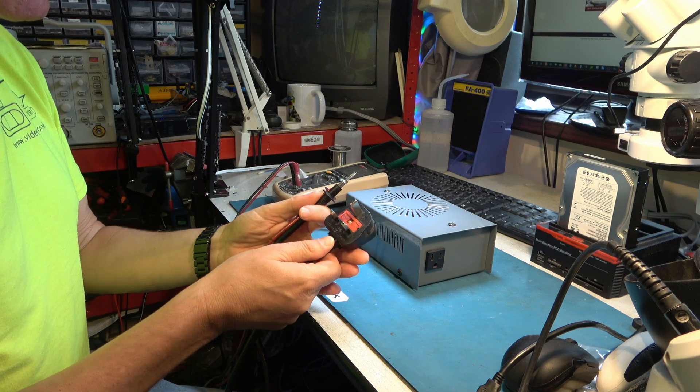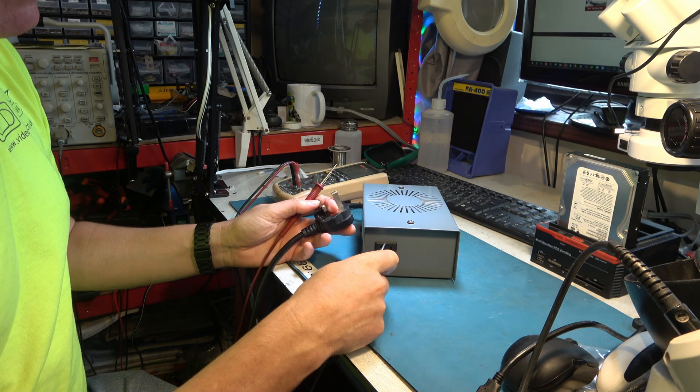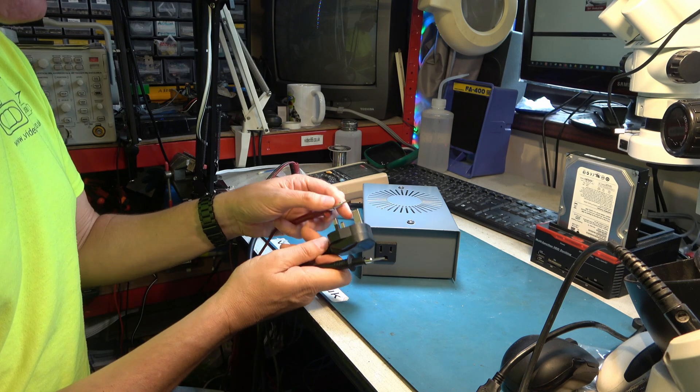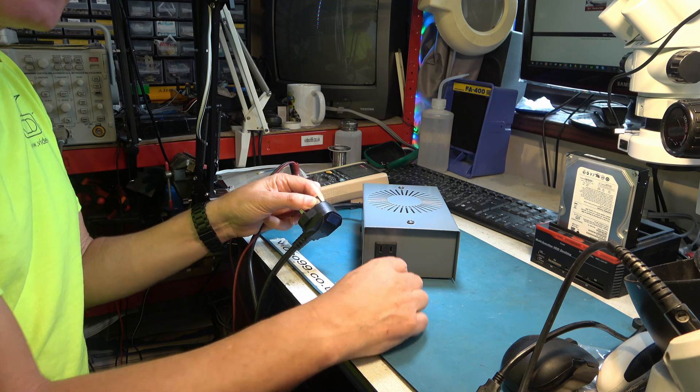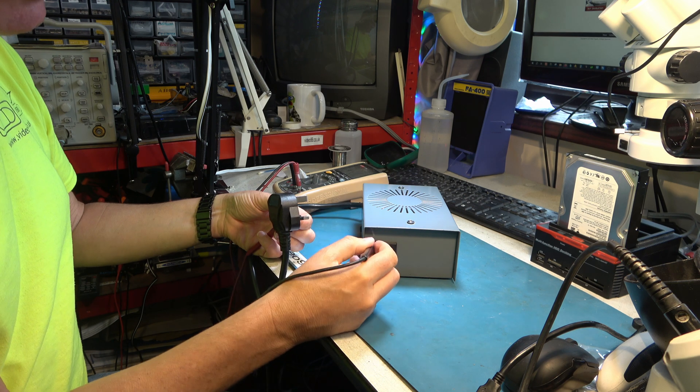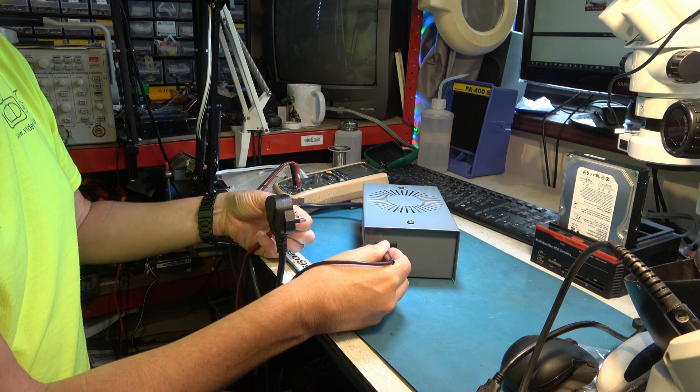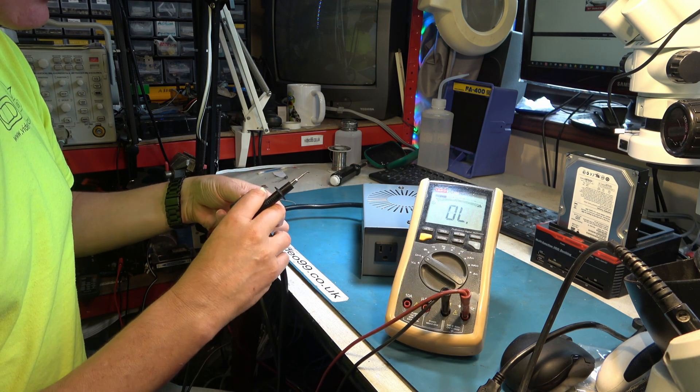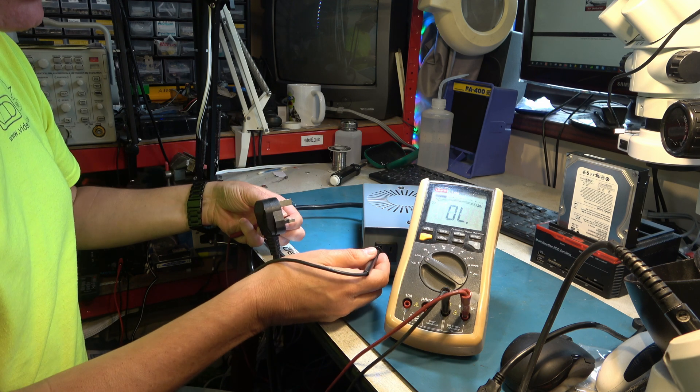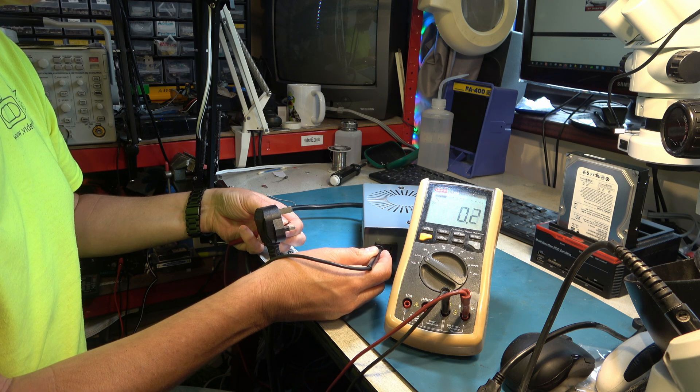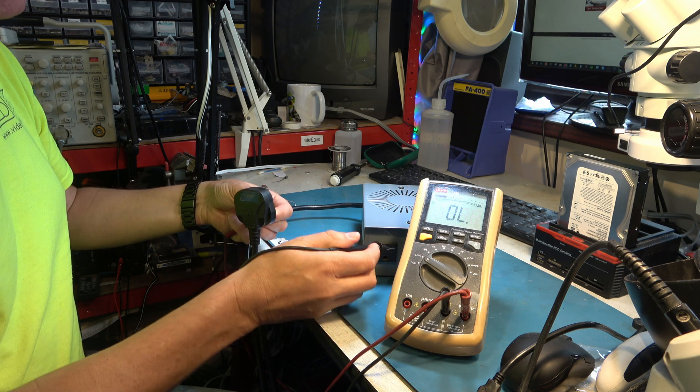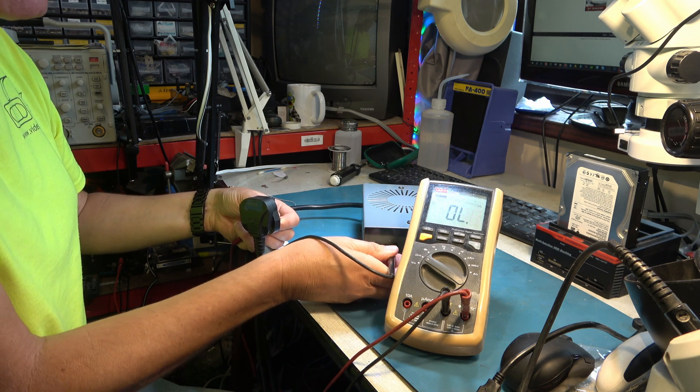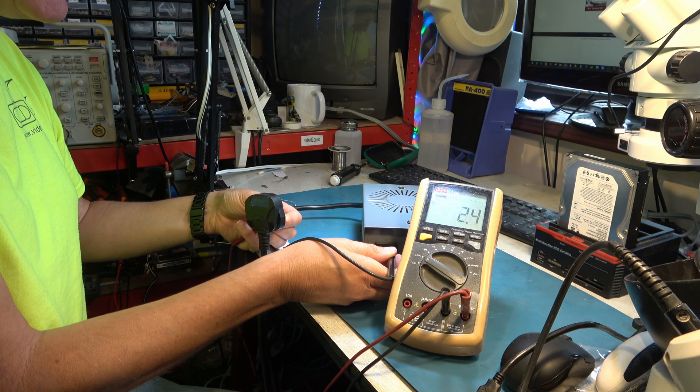Right, let's start by just having a look to see if there's any electrical connection between any of the input and output terminals. Well, we'll start with there should be a connection for Earth. Good start. So we're going to look for a neutral connection. Aha! Yes, there is. Everything will feel like a short circuit with such big windings, but if we look on the neutral connection and this side of the outlet, we're seeing a fraction of an ohm. So neutral is shared. Right, but the live connection will have many ohms, or some ohms, okay, a few ohms due to the extra windings.